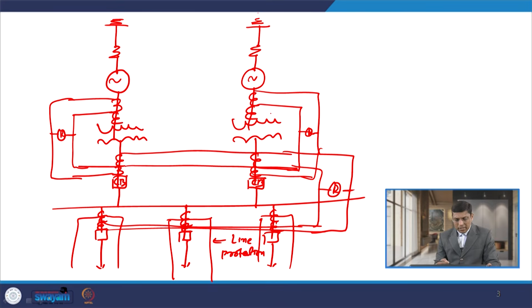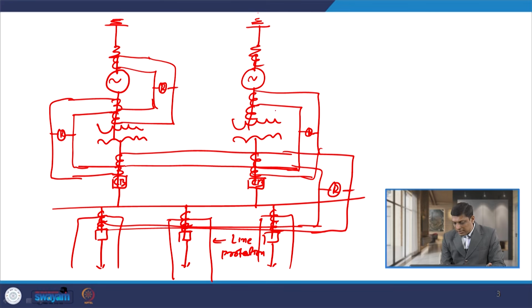Similarly, we have to overlap the generator protection zone with the transformer. So, I put the CT on the bottom side of the generator protective zone CT, somewhere here. So, I have to connect the generator relay somewhere here and same way on this side also I have to connect the generator protection relay. So, here I have to connect the generator relay on this side. So, in this way all the zones are overlapped.